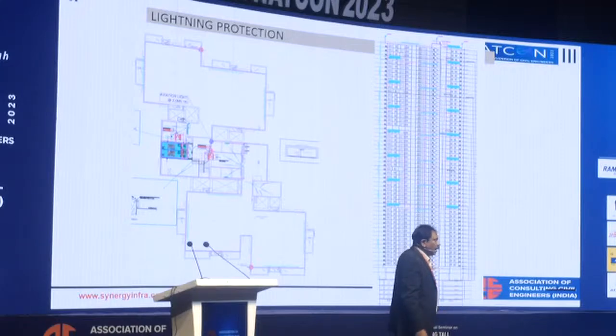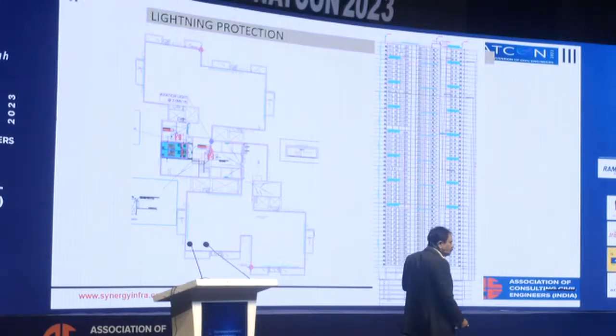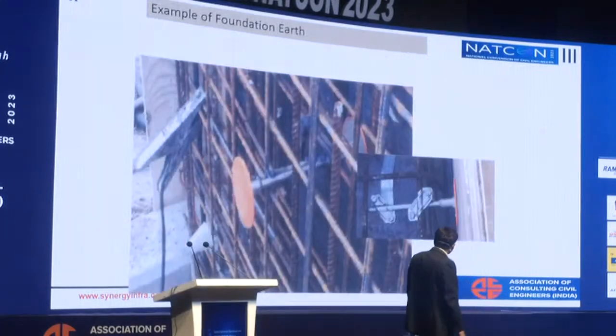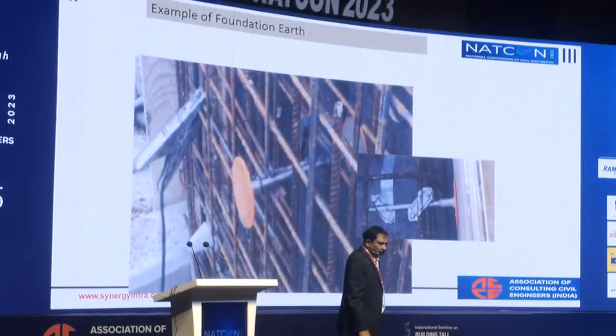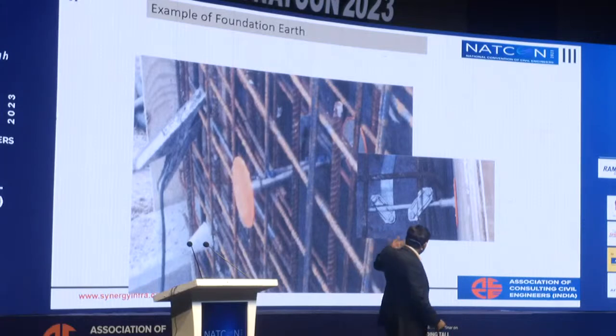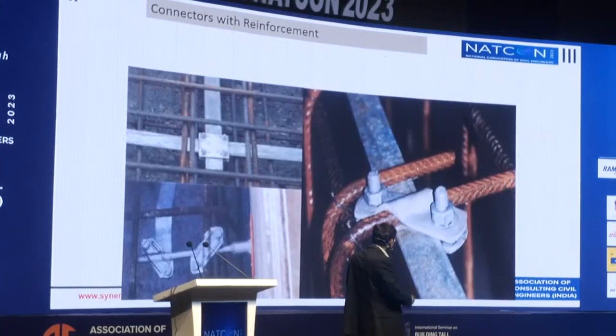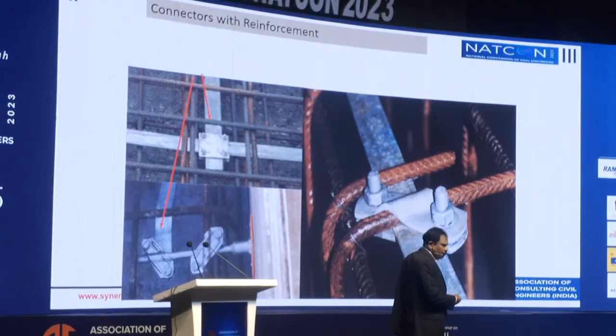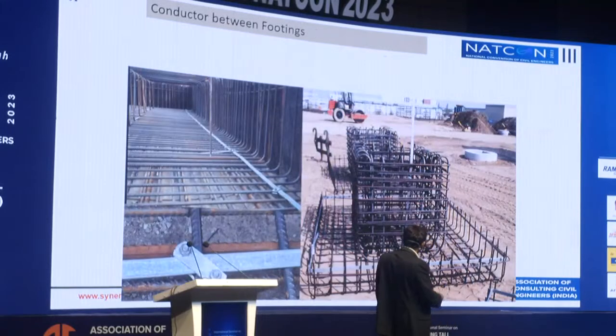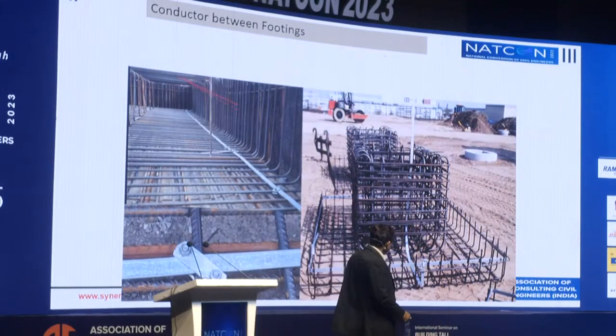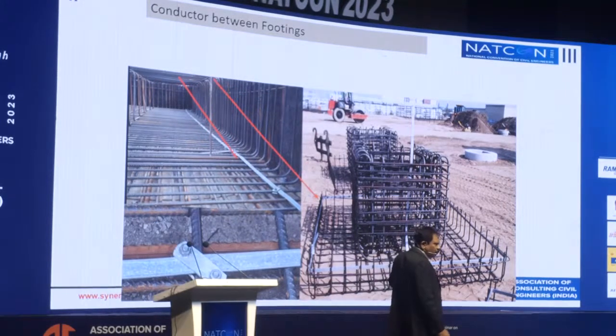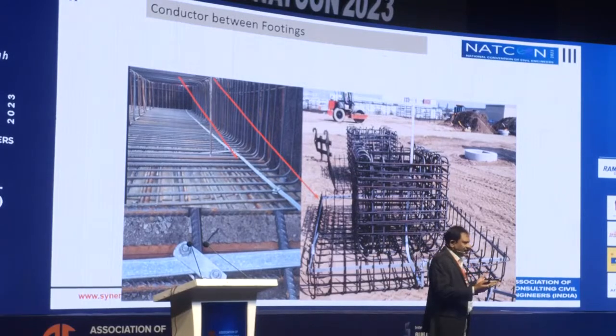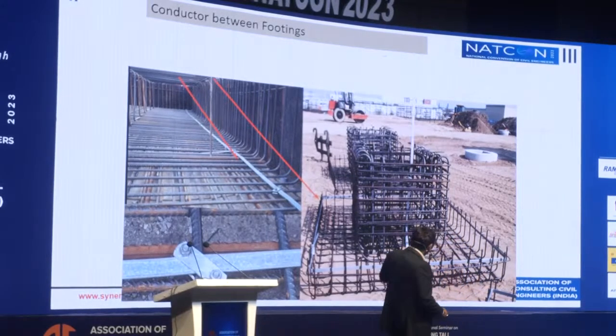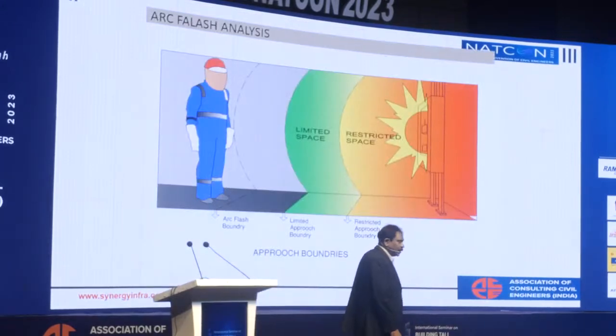This is based on IS 62305, which was also released around 2015-2016. This is how we provide struts for the reinforcement and connect a strip from there, and how we use connectors for the earthing strips. This is what we used to do, but now we use the same reinforcement conductor itself, which could be used for that, and this is how to take a separate conductor if you want. In fact, it's all at the same potential whether you bond it or not, since the distance between all these conductors is hardly anything and we're taking support from that, so it doesn't differ in any way.